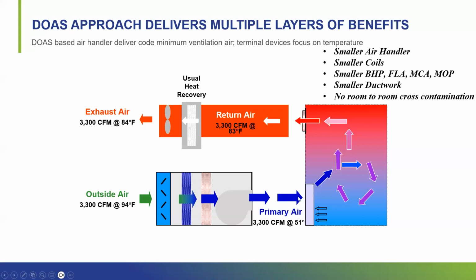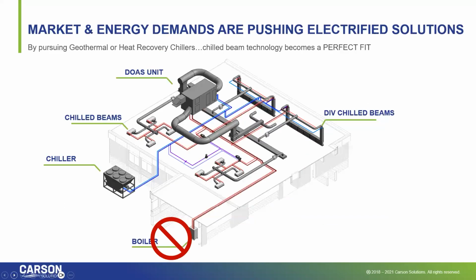delivering just the ventilation air to the space. Typically, there's a recirculation or entrainment at the terminal device where that supply air is then delivered to the space and then ultimately exhausted. And now we recapture that energy. But the takeaway is we have a smaller air handler, smaller coils, smaller electrical requirements. We have smaller ductwork, and we have no cross-contamination from room to room with a DOAS system.